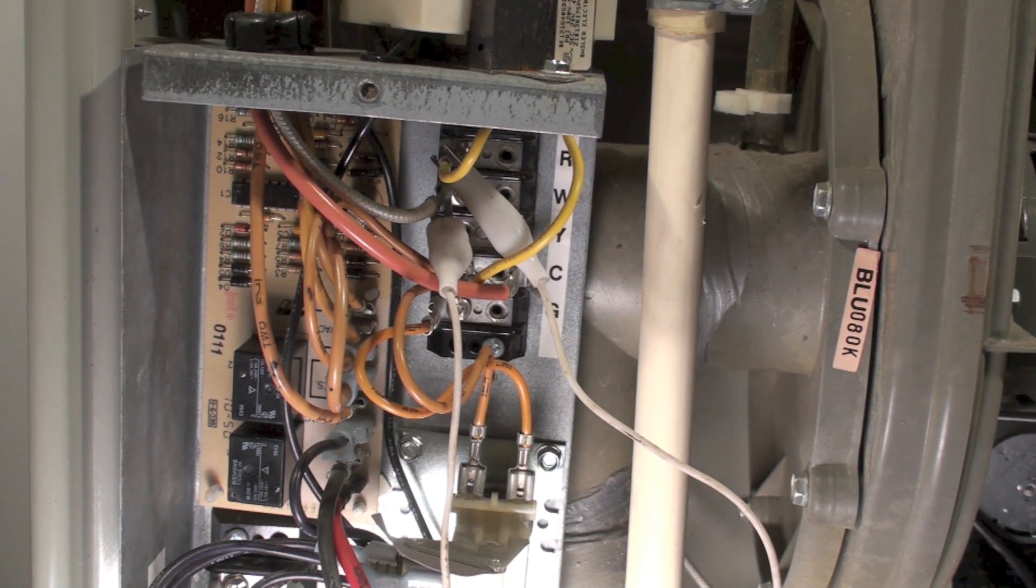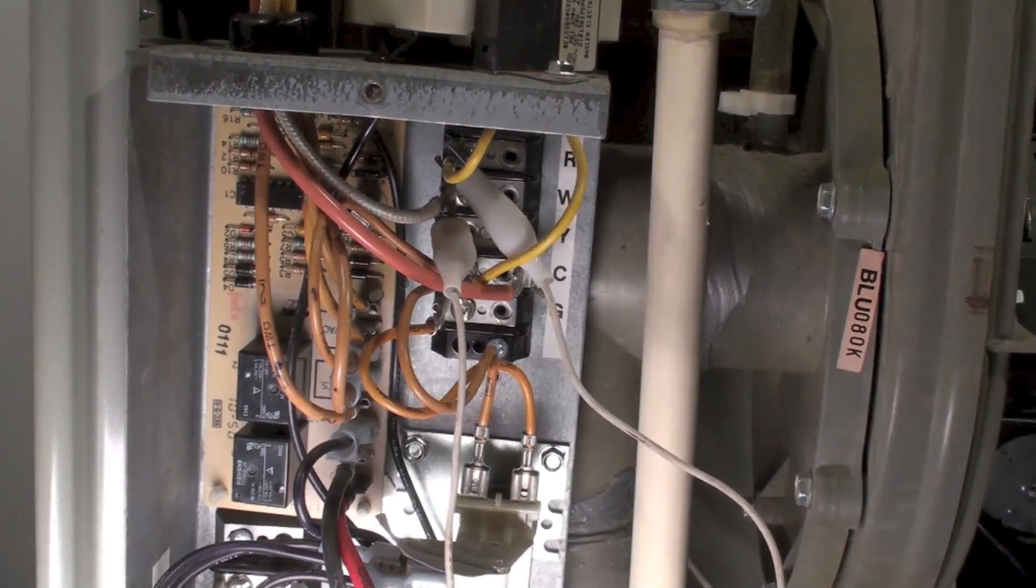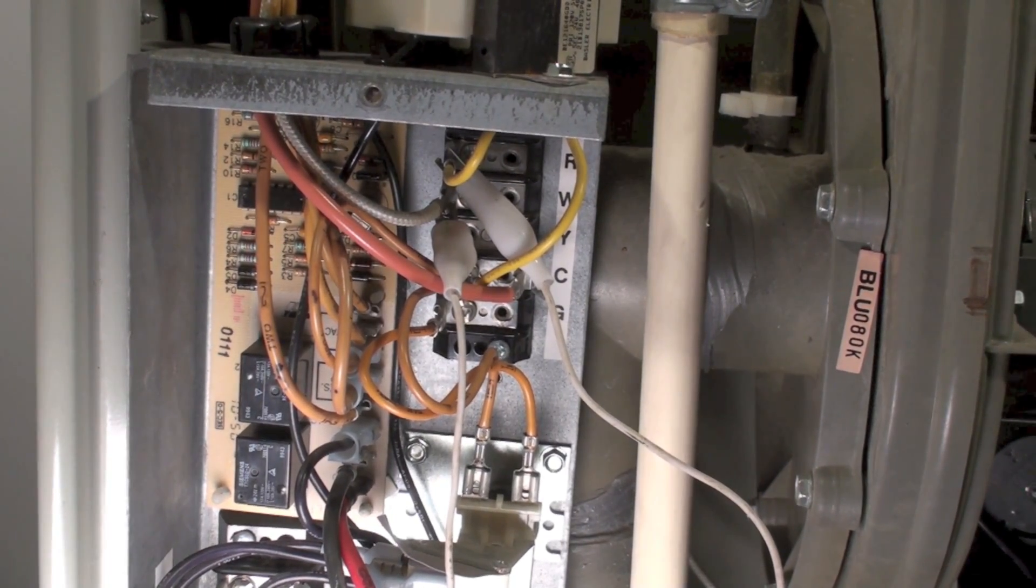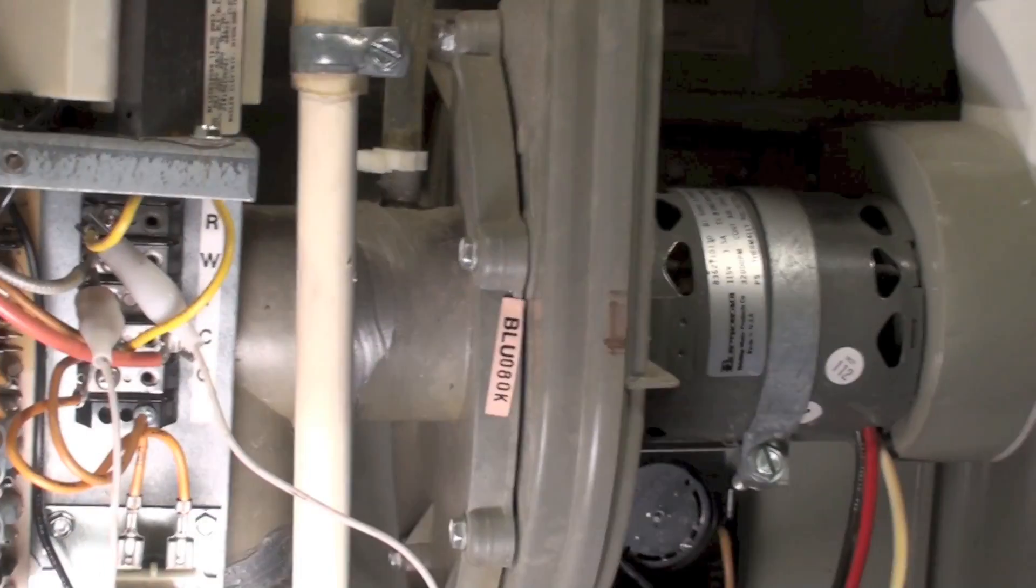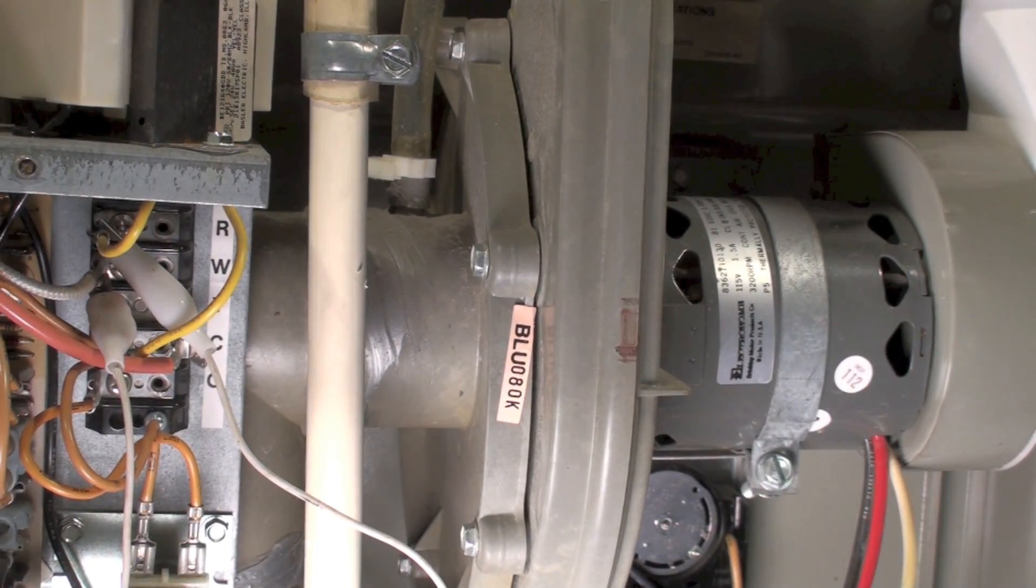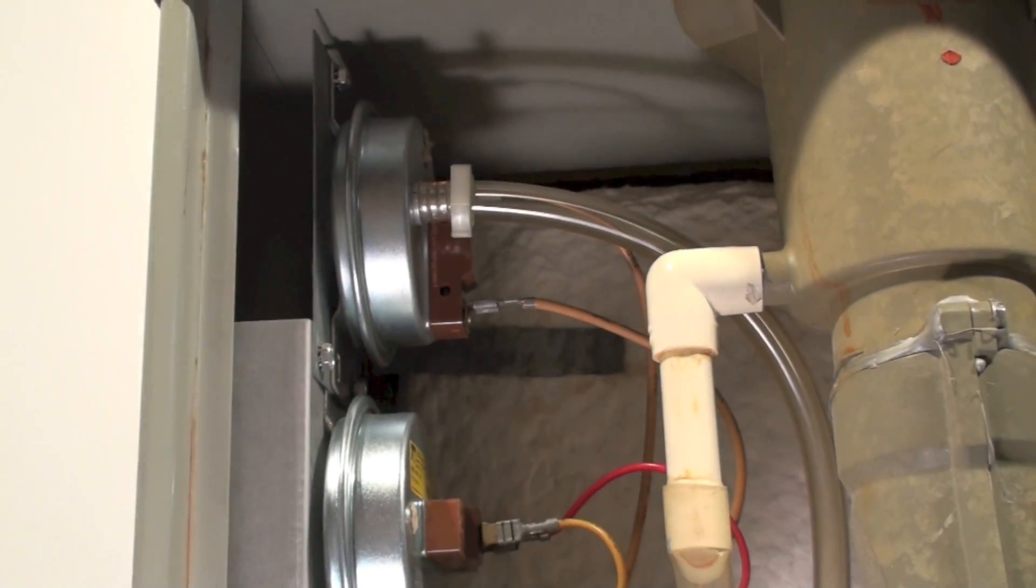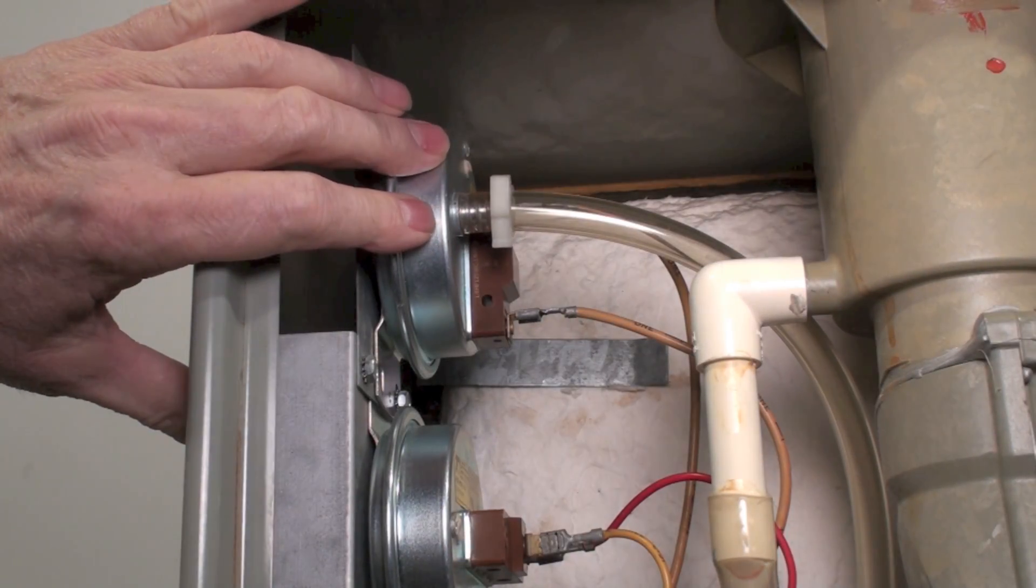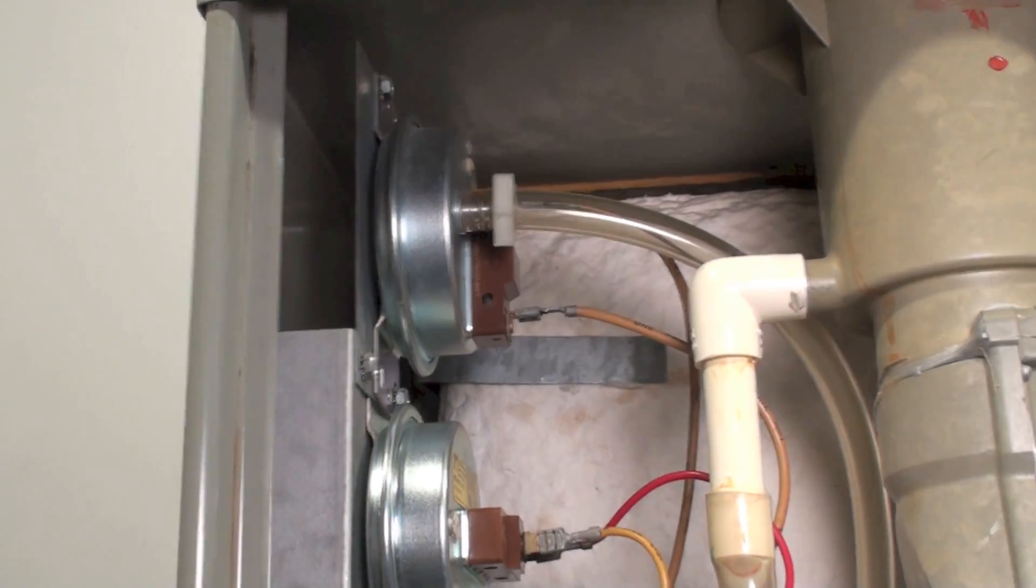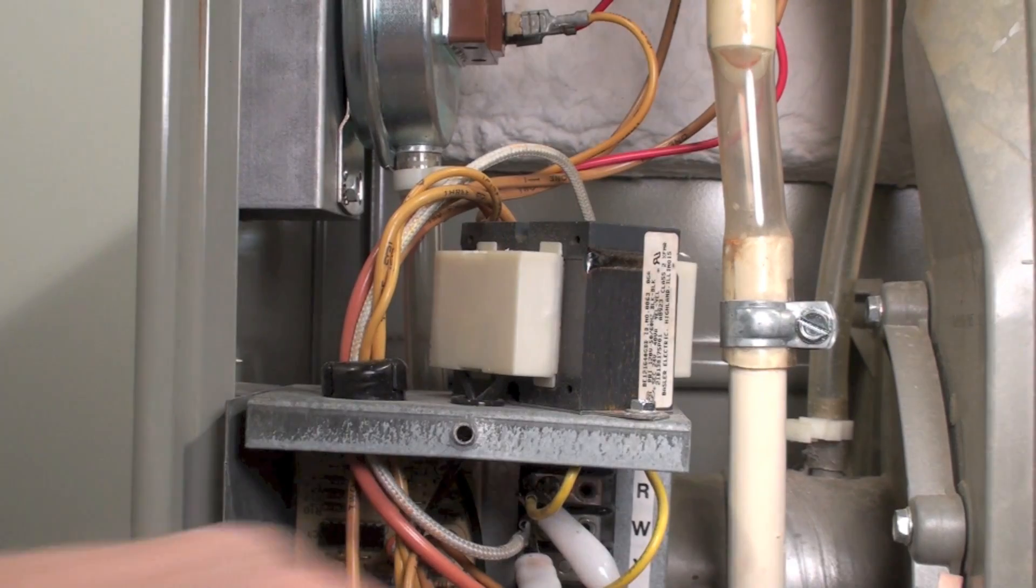I'm going to explain how that works. When power gets to this little board, it turns on high speed of the inducer, which is right there. Then we have this pressure switch hooked right to the inlet. See, it goes right to the inlet of the inducer.